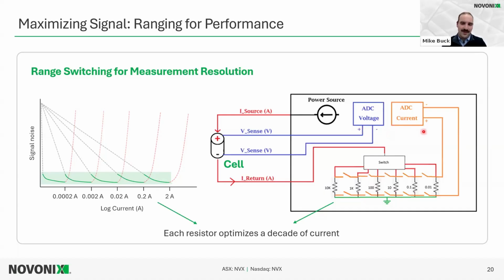But when it comes to measuring the current through the cell, we have to do what's called ranging. Ranging involves setting up a switching network to measure a shunt resistor in line with the cell, detecting how much current is flowing in and out as the current source circuitry pushes and pulls. We need ranges because without them, the measurement window wouldn't be operable. So as you can see on the left, we have ranges to source and sense different levels of current, because a single range wouldn't give us enough sensitivity across all current levels.